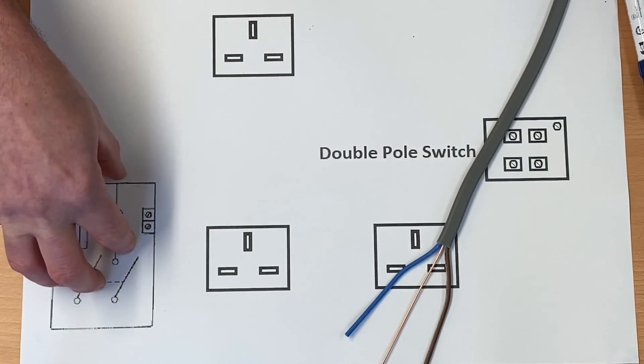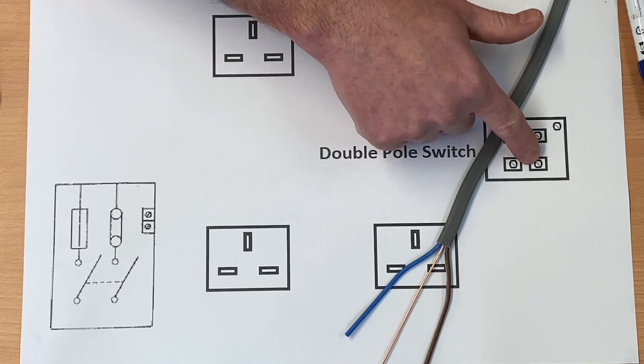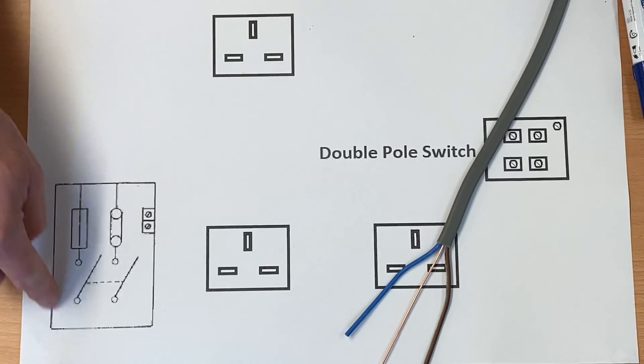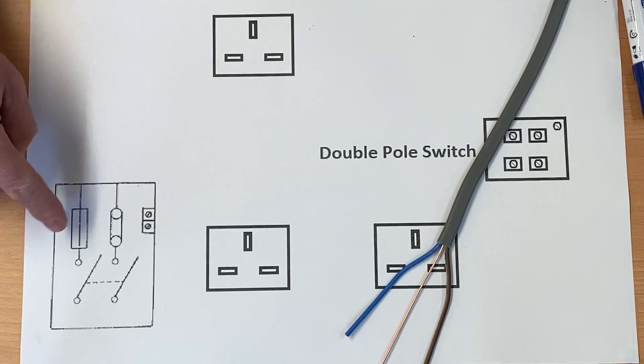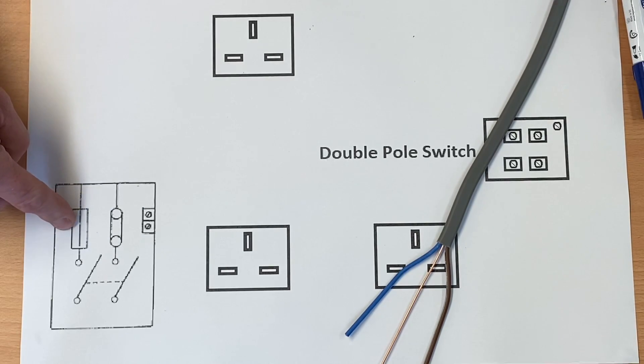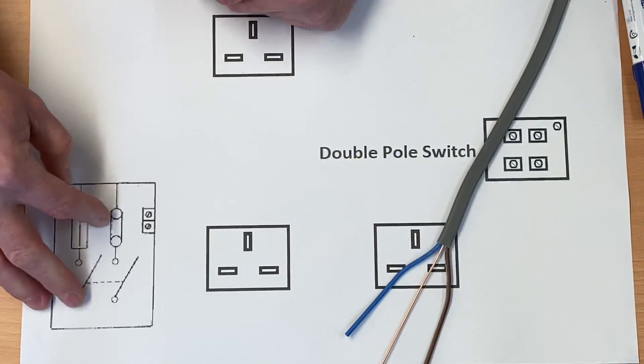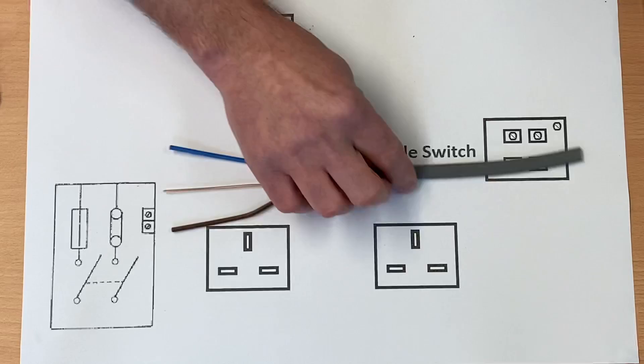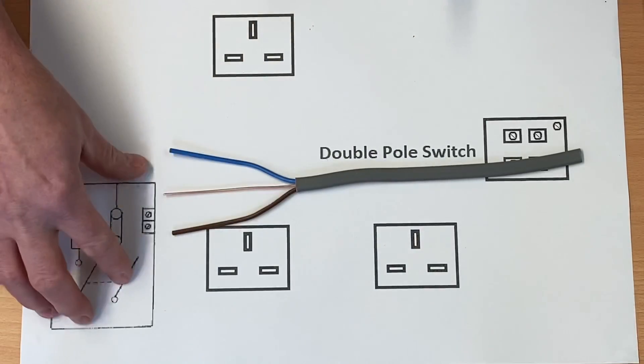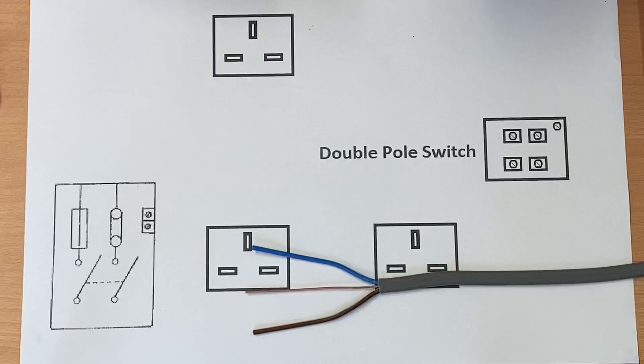So 2.5mm² from the consumer unit to however many sockets Matt did before going through the double pole switch. As always with these wiring diagrams, the connections are not exactly as they would be in the consumer unit - I've got a symbol for a fuse, overcurrent protection device, neutral bar, and the earth terminal within the earth bar itself. If I wire this 2.5mm cable from the consumer unit to socket number one, we'll then go through our double pole switch and explain what's going on there.